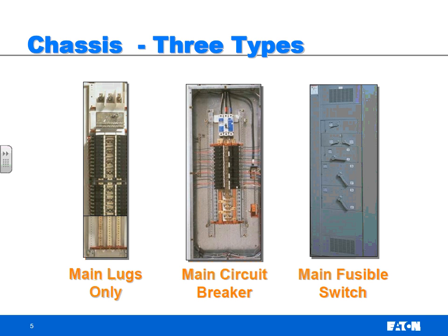So there are benefits to having this main breaker local disconnect. It costs a little bit of money, but has a lot of value to the actual guys who are working on the equipment. Do they come with a switch that doesn't have overcurrent protection? They do. This inherently will come with two types of overcurrent protection built in. They call it a standard circuit breaker, like this one. This is exactly that circuit breaker there.